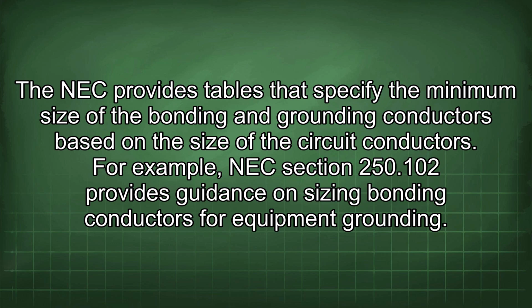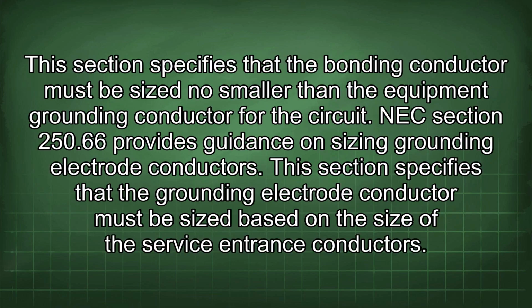For example, NEC section 250.102 provides guidance on sizing bonding conductors for equipment grounding. This section specifies that the bonding conductor must be sized no smaller than the equipment grounding conductor for the circuit. NEC section 250.66 provides guidance on sizing grounding electrode conductors. This section specifies that the grounding electrode conductor must be sized based on the size of the service entrance conductors.